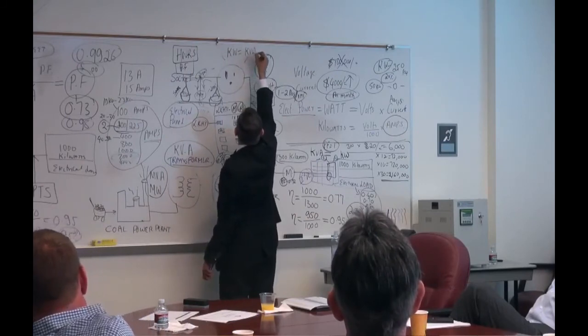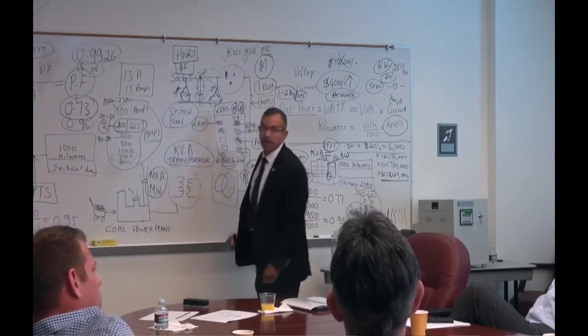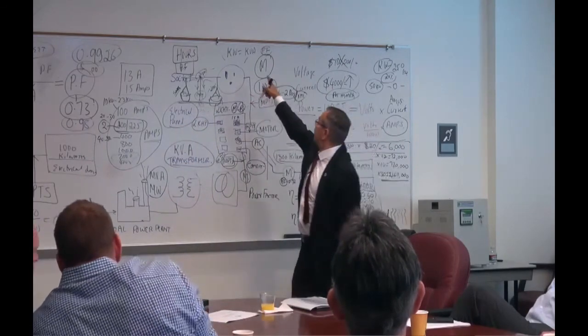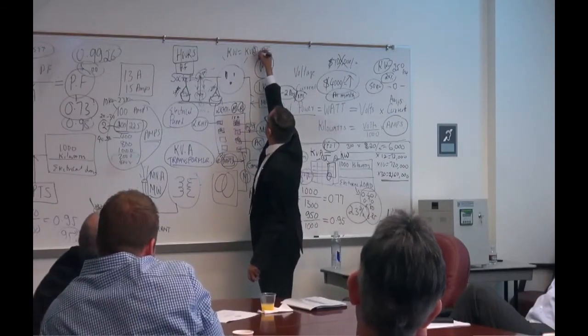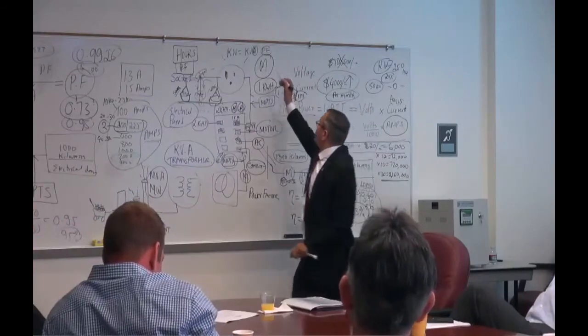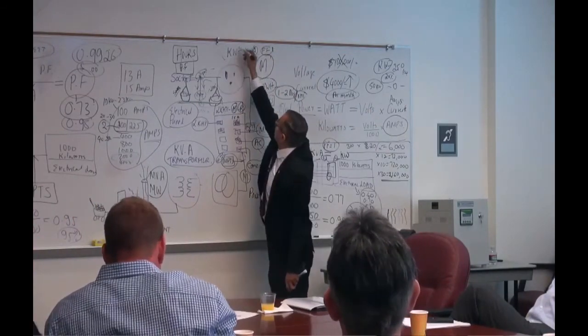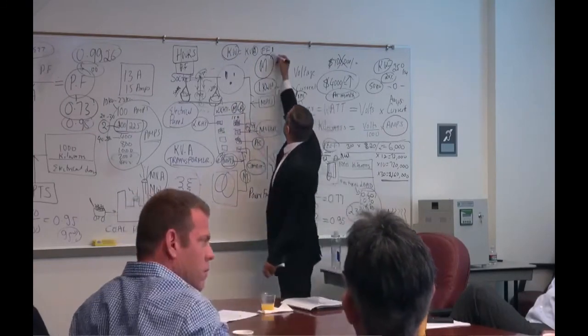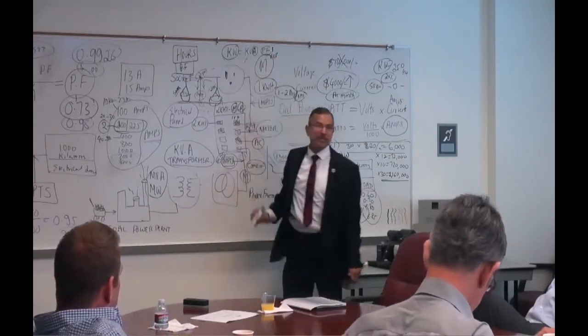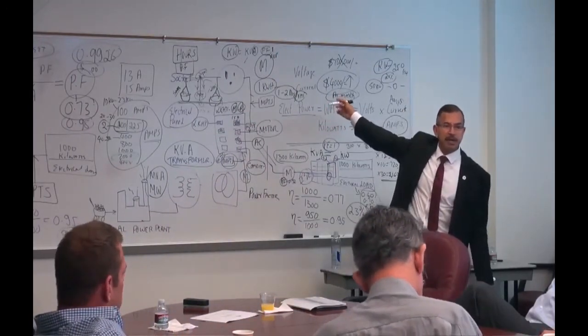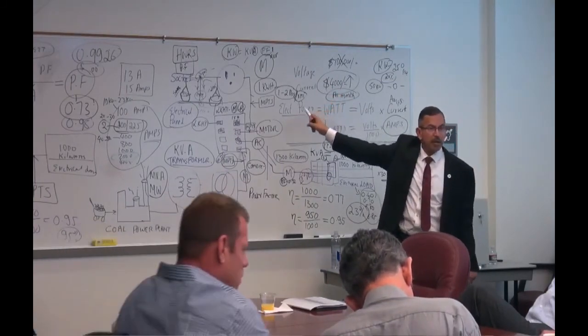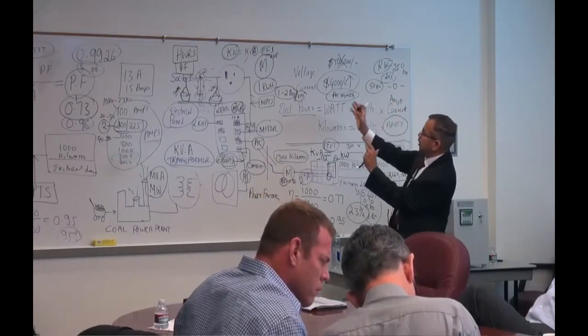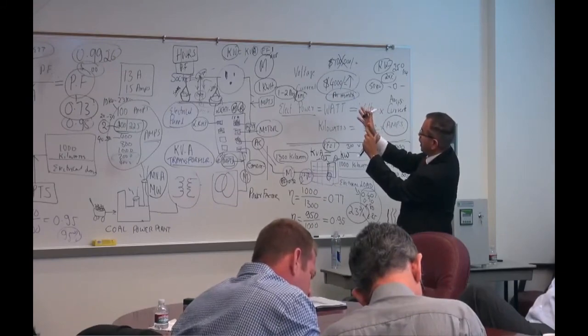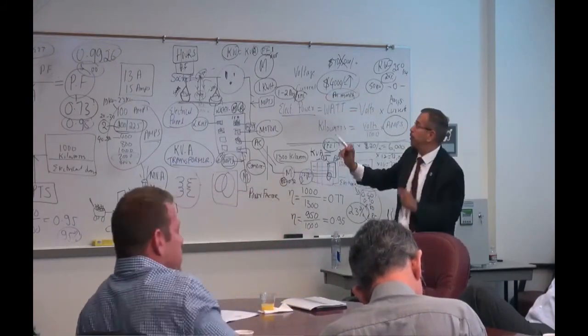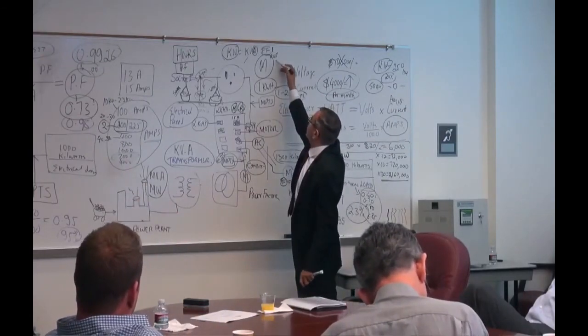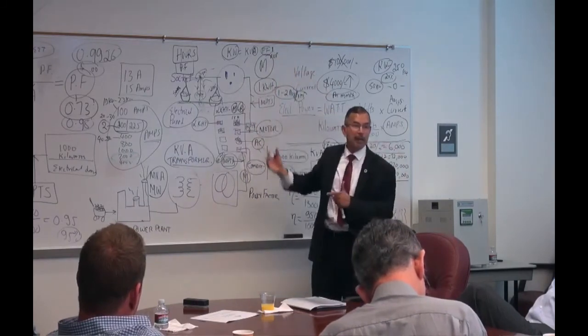KW is equal to KVA times power factor. In this equation, we are going to reduce amps. If this power factor is 1, the kilowatt savings is greater. If it's 0.85, the kilowatt savings is a little bit less. Mathematically, that's the easiest way for me to share that with you, because if you multiply KVA times 1, that is more kilowatts. If you take KVA times 0.85, then it is less. So that's why we are focusing downstream and making sure that this power factor is getting closer to 1. The whole building power factor is going to 1.